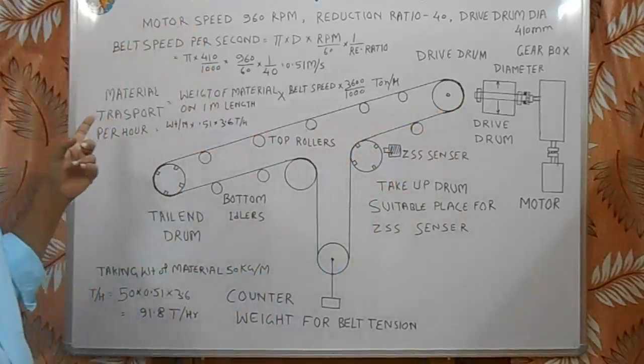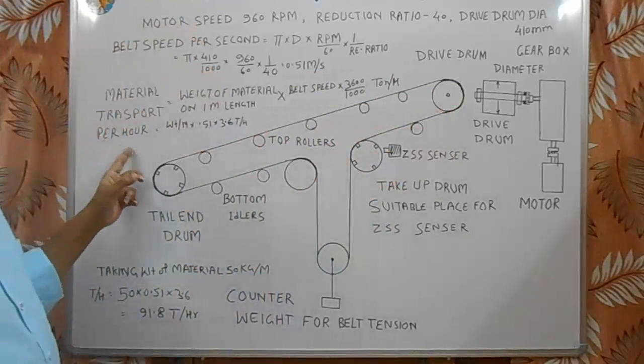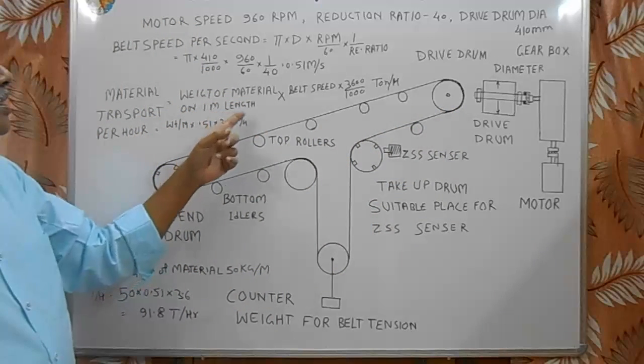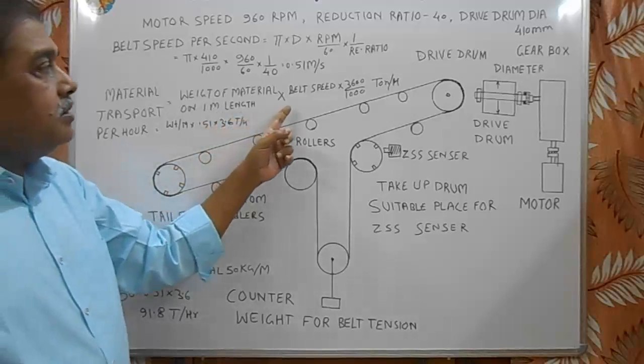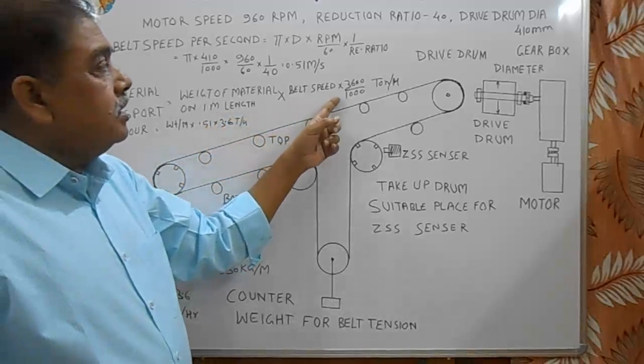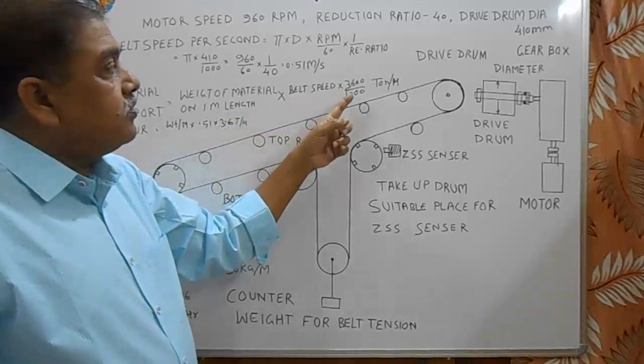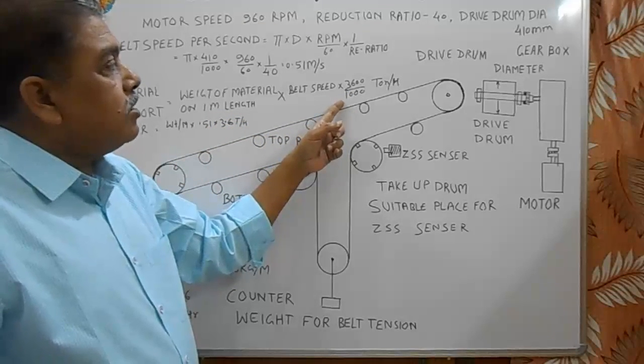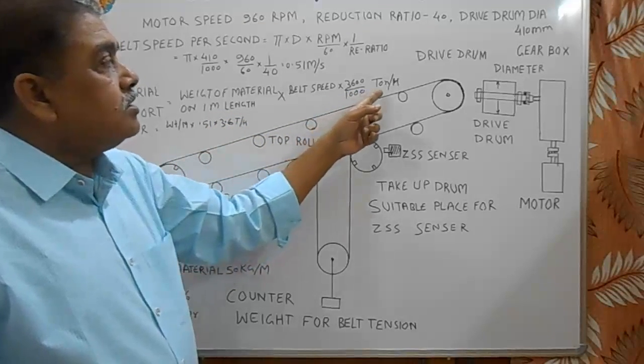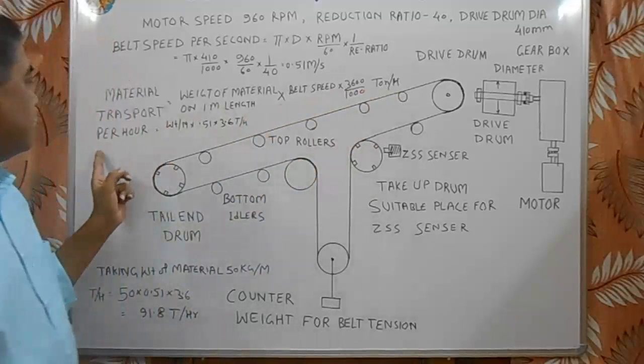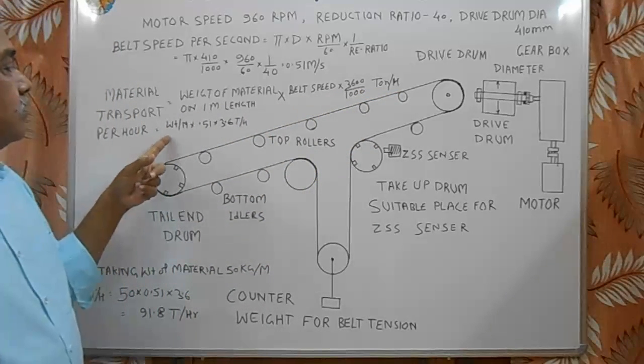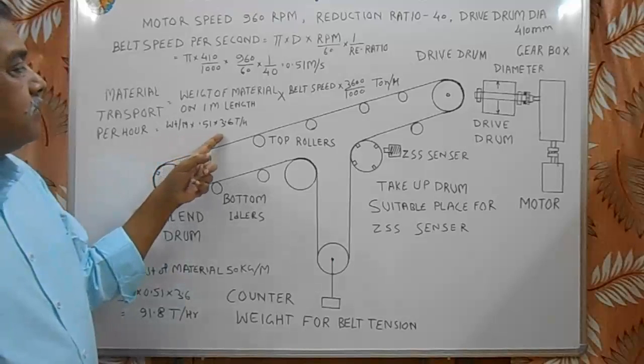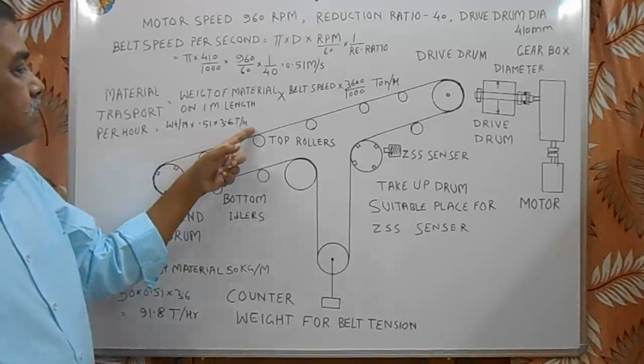So then material transported per hour is equal to weight of material on 1 meter length of the belt, multiply by belt speed into 3600 for 1 hour divided by 1000 to convert it into tons per hour. This is equal to weight per meter multiply by 0.51 multiply by 3.6 tons per hour.